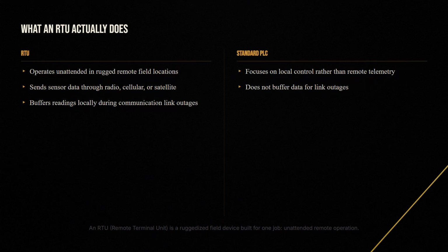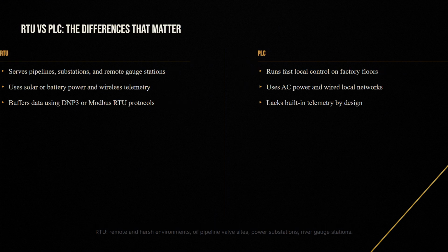An RTU, remote terminal unit, is a ruggedized field device built for one job: unattended remote operation. The RTU reads local sensor data and transmits it to the central SCADA system via radio, cellular, or satellite. If the communication link fails, the RTU buffers readings locally and uploads them when the link is restored. A standard PLC does not buffer data for link outages. RTUs go where PLCs cannot.